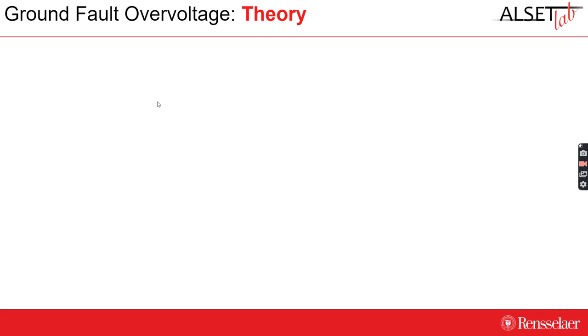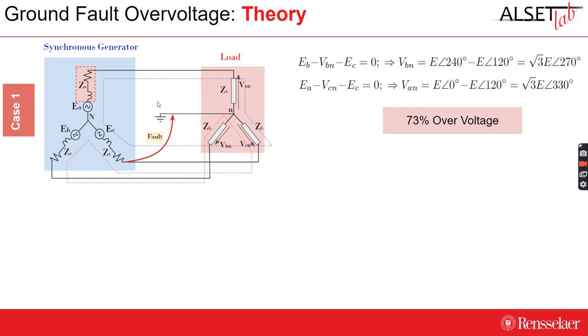For synchronous generators, it is known that whenever a single line-to-ground fault occurs, the voltage level of the unfaulted phases can exhibit an overvoltage of up to 73%. This is theoretically explained in this slide.